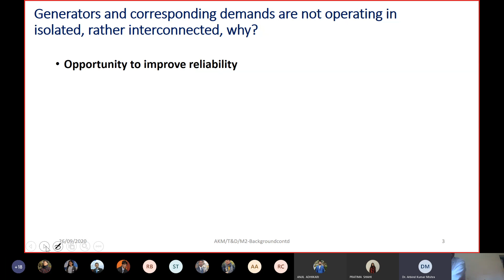For that purpose, we must have sufficient reserve margin. For example, in Nepal we have around 1500 megawatt of demand today. If the available generation is also 1500 megawatt, and we have failure of some line or generator, then we cannot meet that demand. But if we have available generation capacity of say 1800 megawatt, with demand of 1500 megawatt, and we have a failure of one unit of say 100 megawatt, then yes we can meet it, provided our transmission capability allows it. So reliability can be improved, but with reserve capacity of generation as well as transmission.